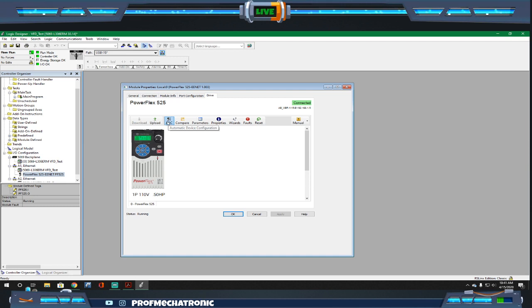Now the next one here is called ADC. ADC is a very cool feature that Allen-Bradley and Rockwell have put into their software. What ADC allows us to do is automatic device configuration. So we can actually store all the device parameters inside the PLC itself. And so if a drive goes down for any reason, we're able to update just the IP address on the drive, add it back to the network, and as long as that drive is compatible with what we've stored before in the PLC, we're able to dump those parameters from the PLC and push them into the drive. So that makes the maintenance of VFDs a lot easier.